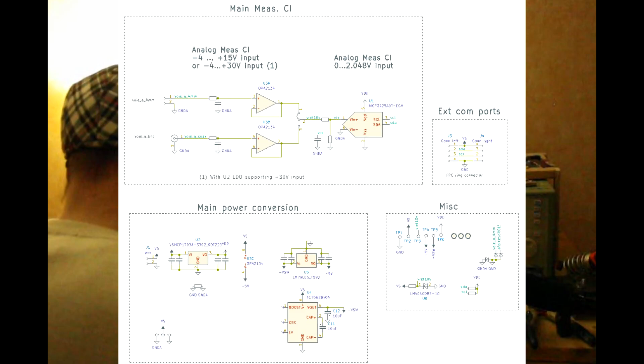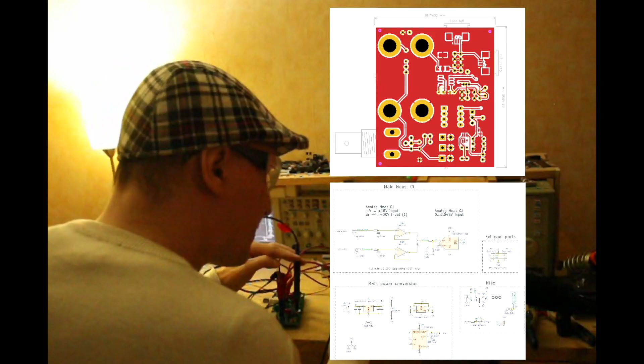We can plug the jumper JP1 between 2 and 3 for the BNC input, or between 1 and 2 for the terminal input, the green and blue terminals. And I have now plugged the jumper for BNC, and I am using this probe, this external probe. The probe is a standard 1 or 10 meg oscilloscope probe. It's working a little bit better on 1 meg.